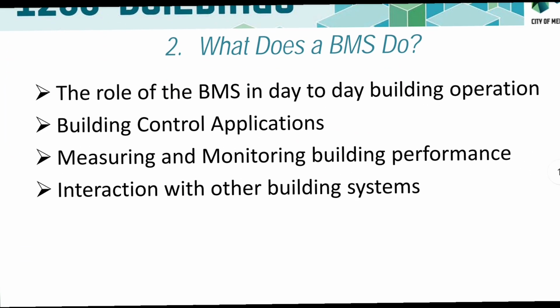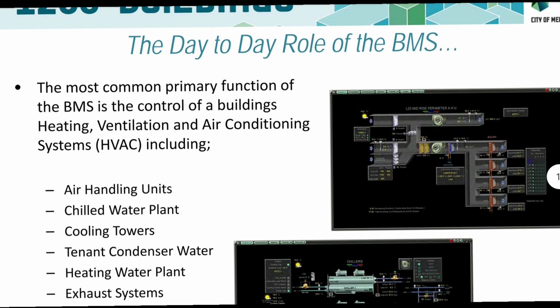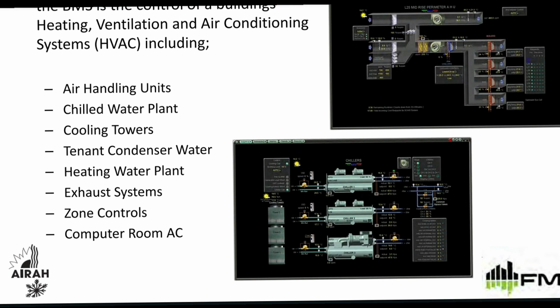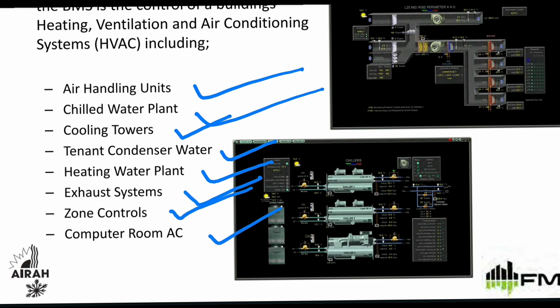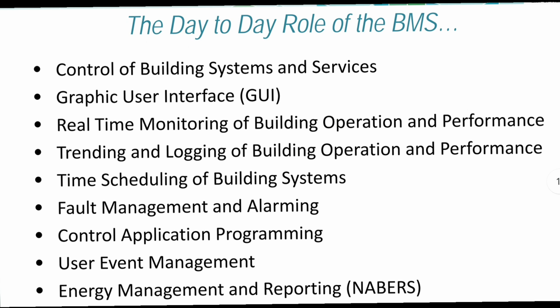How does a BMS work? So let's get started. First, the role of the BMS in day-to-day building operation. Second, building control applications. Third, measuring and monitoring building performance. Fourth, interaction with other building systems. The most common primary function of the BMS is the control of the building heating, ventilation and air conditioning system, HVAC, including air handling units, chilled water plant, cooling tower, tenant condenser water, heating water plant, exhaust systems, zone control and computer room AC.